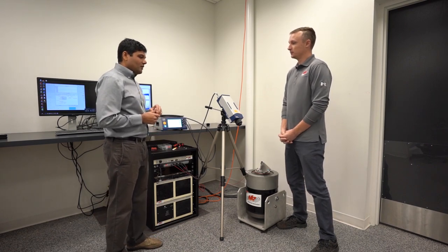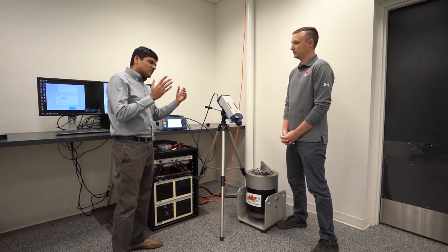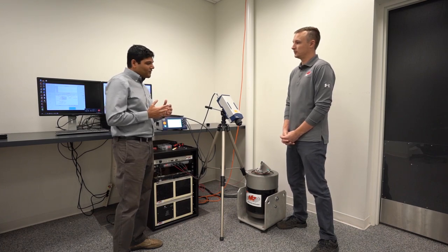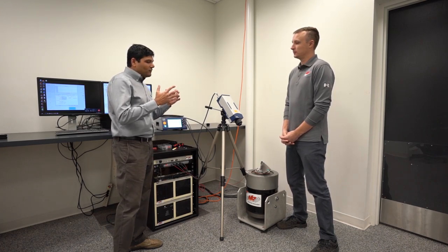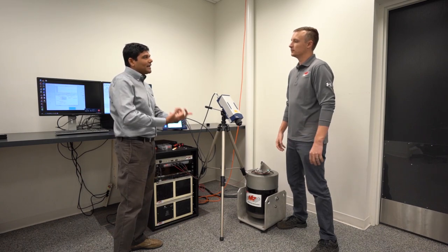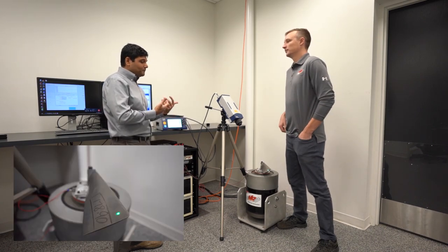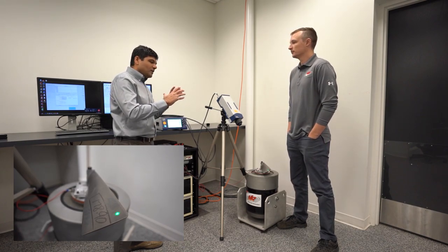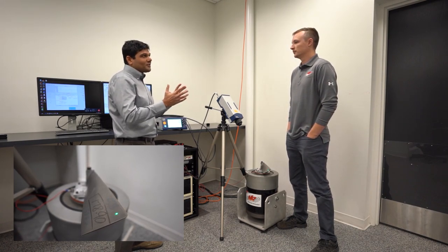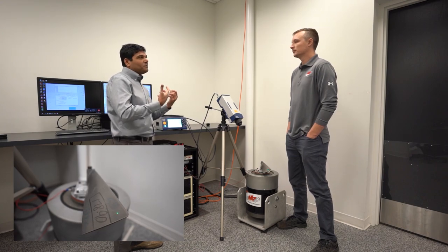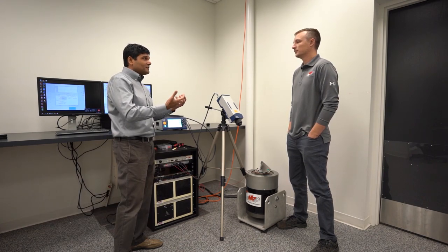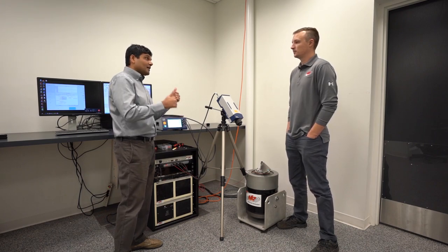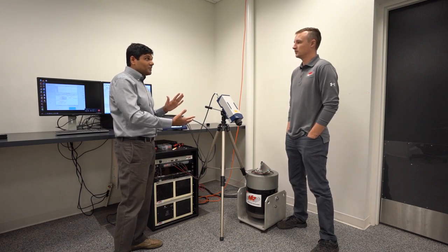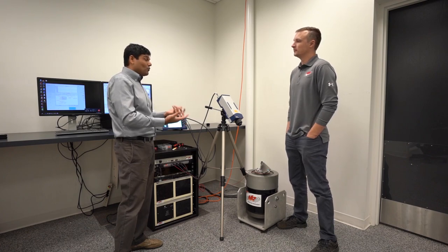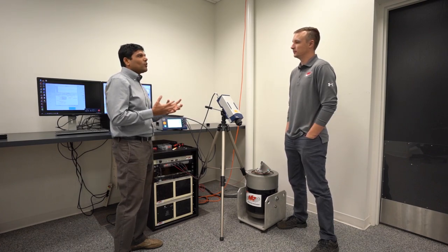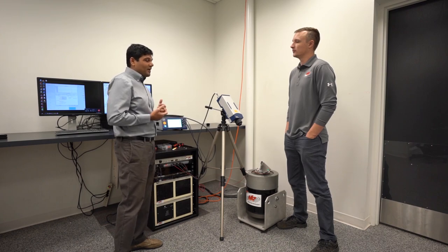So if we go back to the basics, it helps us answer this question, in the sense that a vibrometer is always looking for some light coming back to the sensor, to the detector. So that defines my surface. How can I get more light back? Either my surface is nice and reflective and my alignment is good, so all the light's coming back, or my standoff distance is less, so that more light is coming back. So you try to do whatever you can to increase the amount of light coming back.